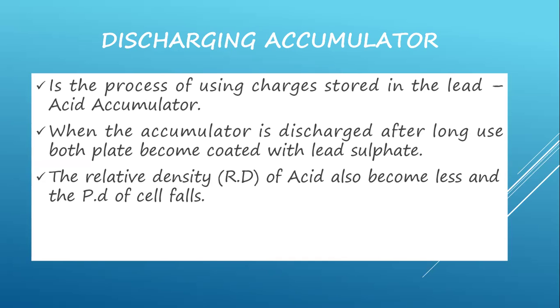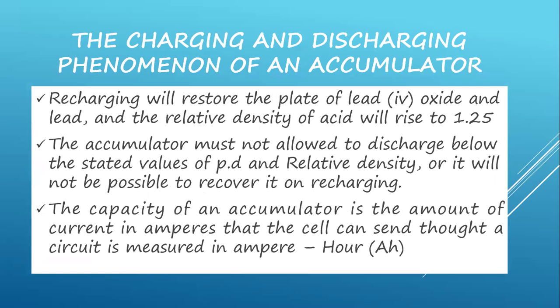So generally here we're discussing the charging and the discharging of the lead acid accumulator, as we previously discussed the structure of this accumulator. Now, the recharging process will restore the plates to lead oxide and lead, and the relative density of the acid will rise to 1.25.